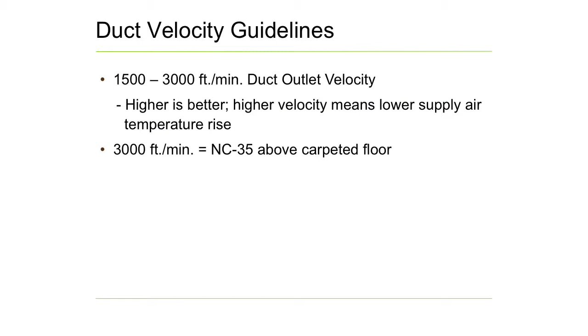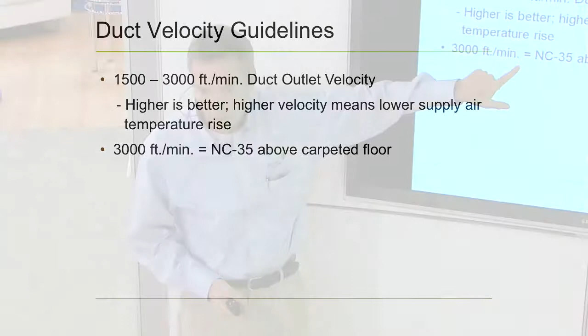Here we've got low pressure, so we've run some tests, also in the book, showing that we can up that ante from 1,500 to more like 2,000 to 3,000 feet, and still maintain an NC of 35 at the end of the duct. We've tested that on real world conditions. So we just suggest higher velocities.